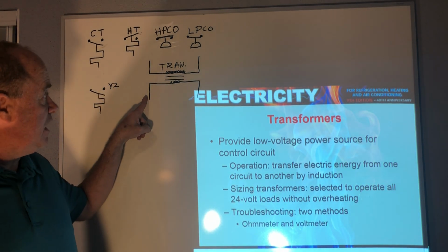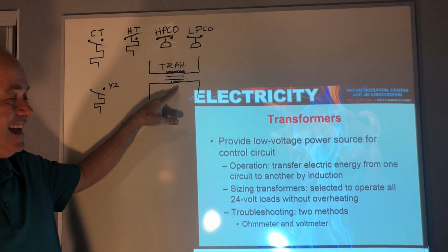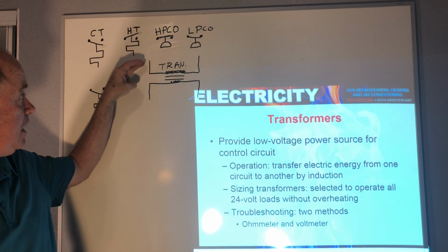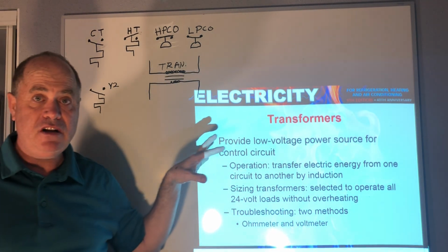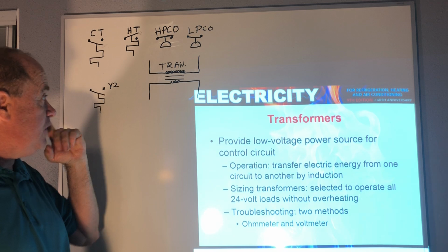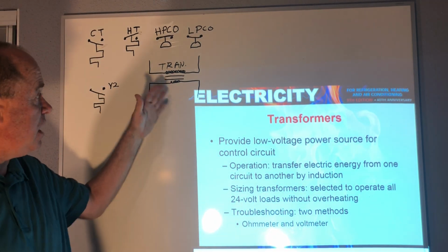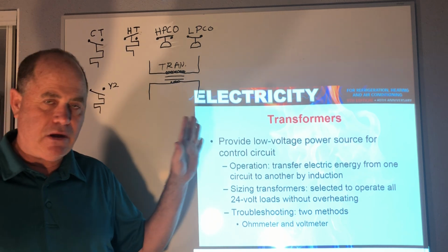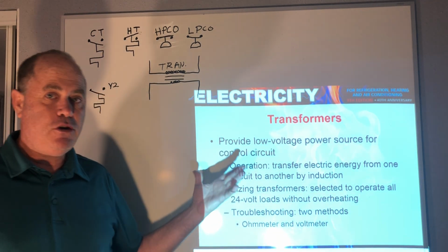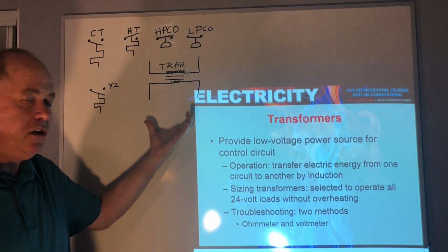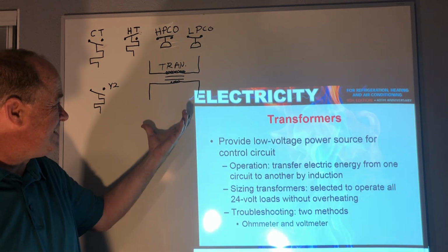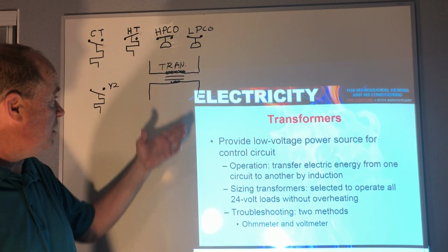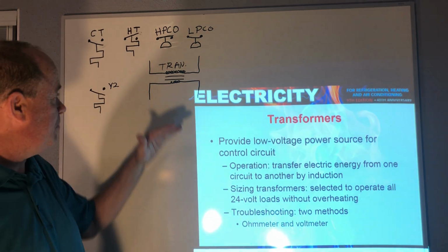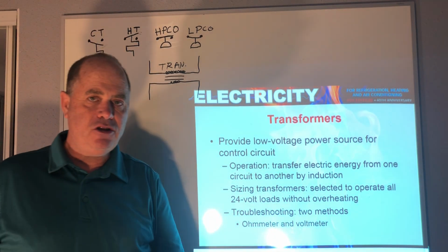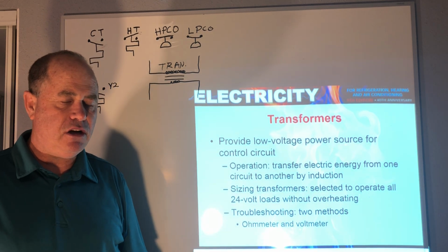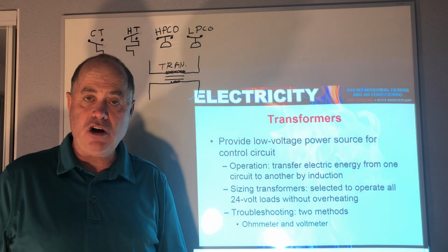And here we have the electrical symbol for the transformer with a primary and a secondary. If you're getting voltage in the top, like your primary 230, and you're not getting voltage at the bottom of 24 volts, if there's a reset, you can try your reset on the thermostat. But if there's not, the transformer needs to be replaced. Now, before you replace the transformer, you should check to make sure none of the wires or components in the secondary are grounded or so badly shorted that they'll burn up the new transformer. But that's the operation, dropping it down generally to 24 volts inside of our units to control things like thermostats and contactor coils, etc.